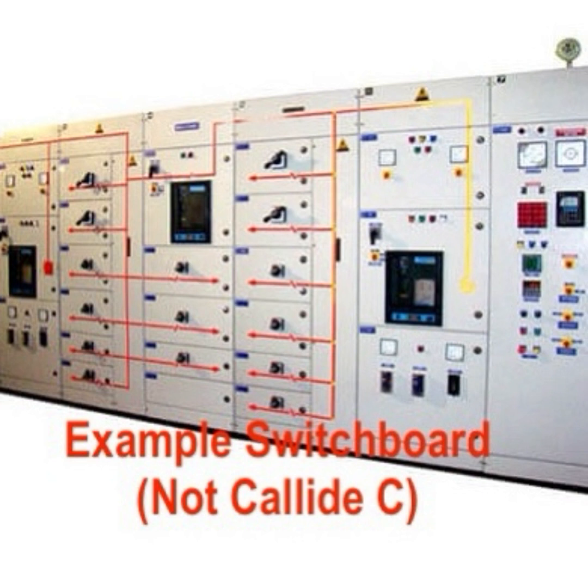Forgetting the GCB for the moment, the DC power would also have allowed the backup diesel generator to close onto the emergency 415-volt AC bus, thus supplying power to critical systems, thus avoiding the worst-case outcome. Forgetting all of that, they also could have closed the station emergency 415-volt AC bus ties to cross-feed the unit 415-volt AC board once the diesel genny was up and running.